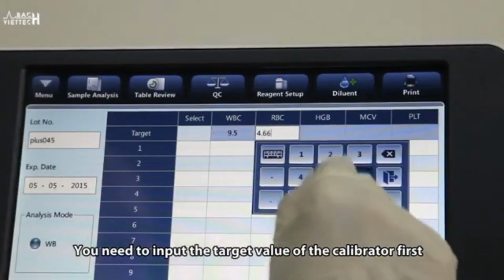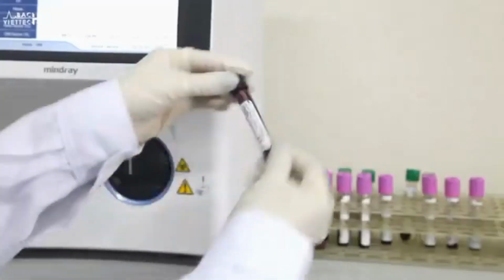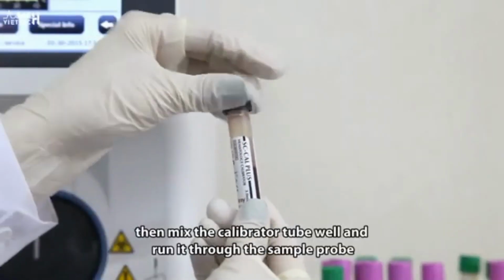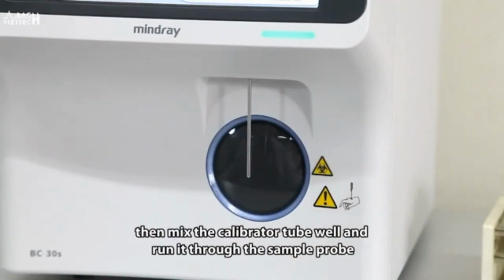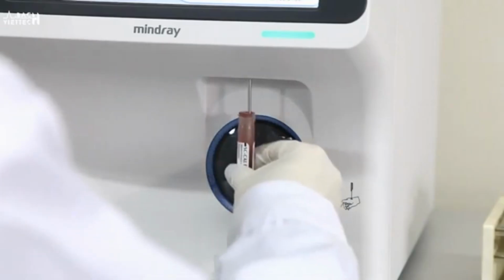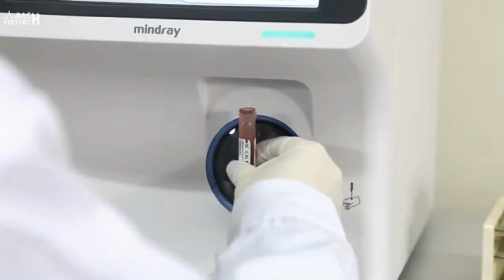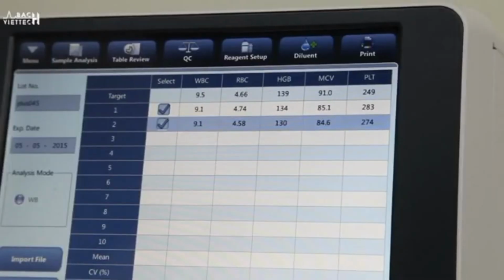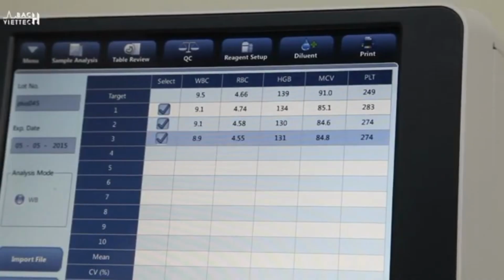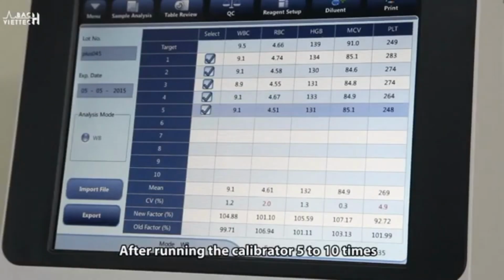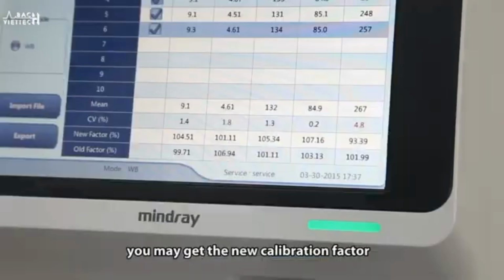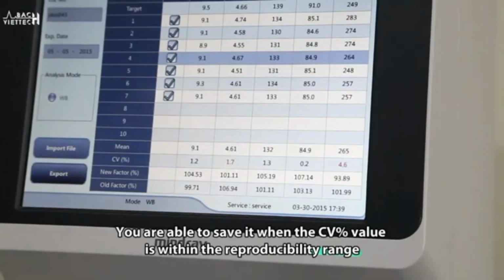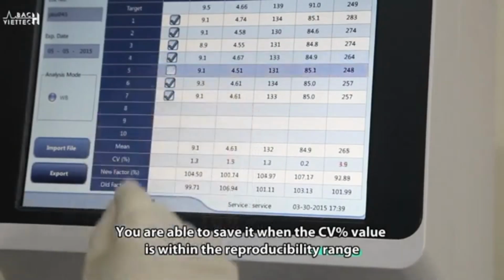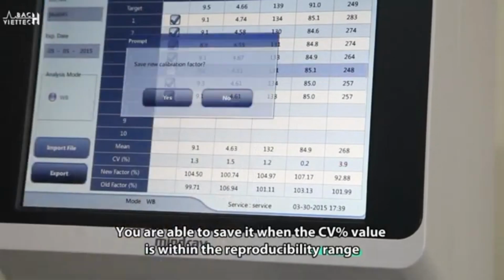You need to input the target value of the calibrator first. Then mix the calibrator tube well and run it through the sample probe. After running the calibrator 5 to 10 times, you may get the new calibration factor. You are able to save it when the CV% value is within the reproducibility range.